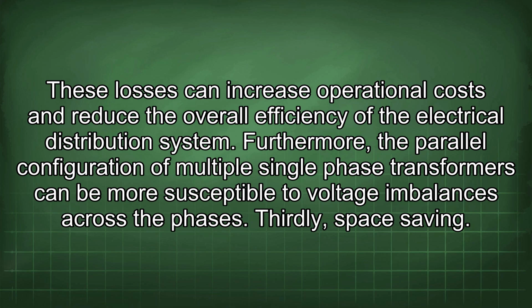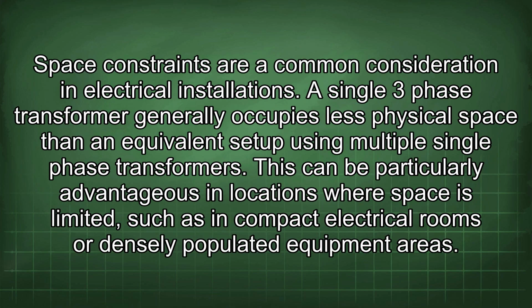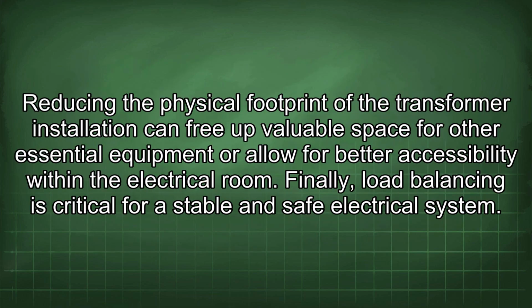Thirdly, space saving. Space constraints are a common consideration in electrical installations. A single three-phase transformer generally occupies less physical space than an equivalent setup using multiple single-phase transformers. This can be particularly advantageous in locations where space is limited, such as in compact electrical rooms or densely populated equipment areas. Reducing the physical footprint of the transformer installation can free up valuable space for other essential equipment or allow for better accessibility within the electrical room.